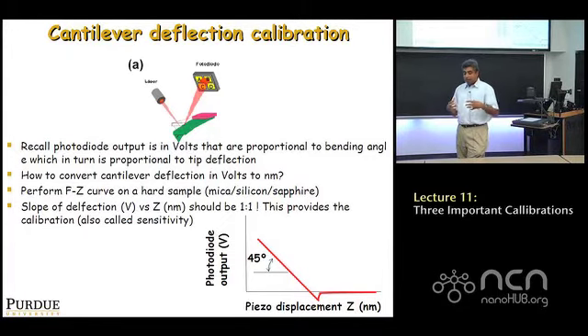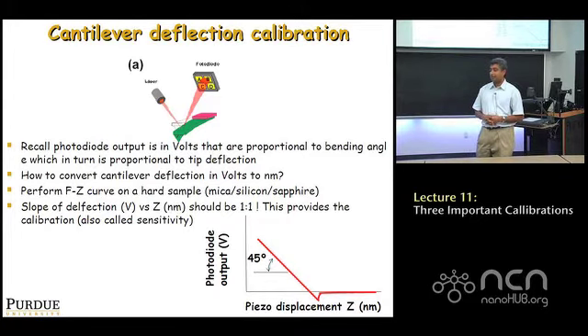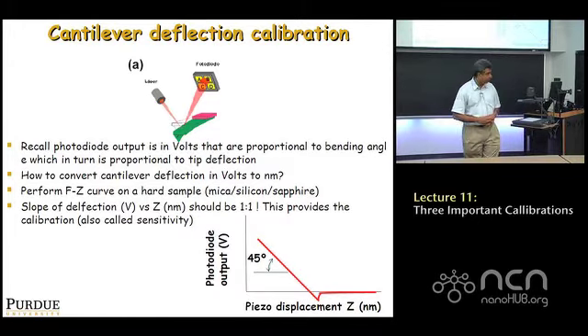So whatever object whose stiffness you're measuring, your cantilever deflection calibration has to be done on a sample that's much, much stiffer than that. And if, God forbid, you're asked to measure the elastic modulus of mica, which I hope none of you is asked to do, it's terrible and very difficult. It's very stiff. You would have to use something like osmium or sapphire, which have a Young's modulus at least 4 times greater than what you're trying to study, okay? So keep that in mind. Of course, if you're doing soft samples, silicon is typically okay.